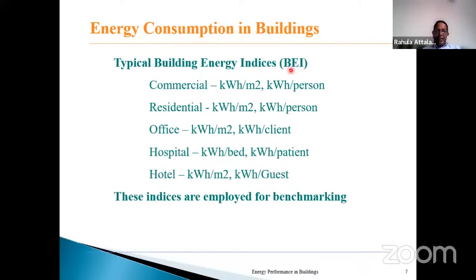So this is very important for BEI, Building Energy Index or indices, or sometimes we call it Energy Use or Energy Utilization Index, EUI. You will see down the line what these are and why they are important. BEIs are important, energy intensity. Depending on the building type, we can define the typical building BEIs. For example, a commercial building has commercial activities like supermarkets, slightly different from hotels in our classification in Sri Lanka. Banks, offices, supermarkets, departmental stores, etc. The index is kilowatt hours per meter square for a period, maybe per year or per month. Usual is kilowatt hours per meter square per year or a month, because it has to be some substantial number.